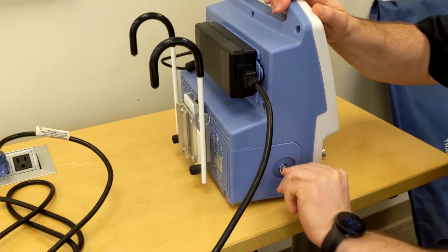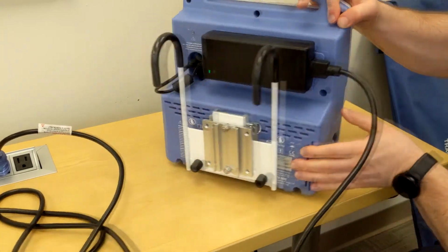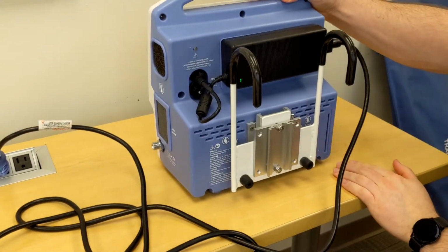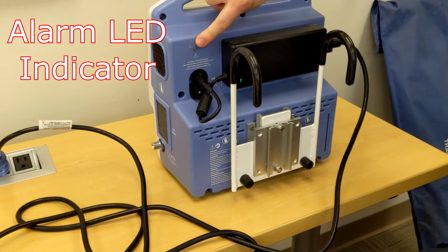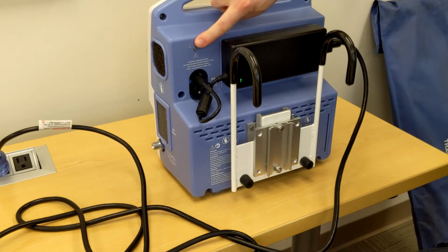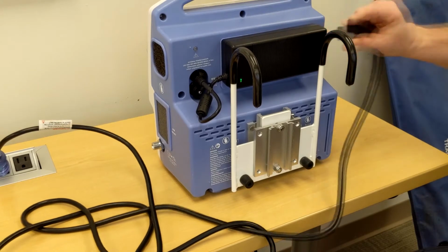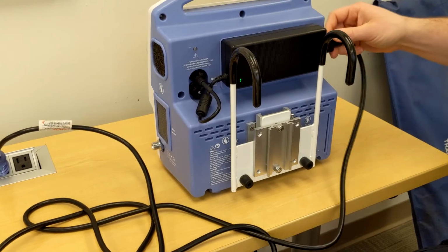When running with two batteries installed, approximately 20 minutes of operation will remain after the second low battery alarm is triggered. An alarm LED indicator is located here, but we'll go over alarms later in this video. This black box is the AC adapter and can be unplugged here.